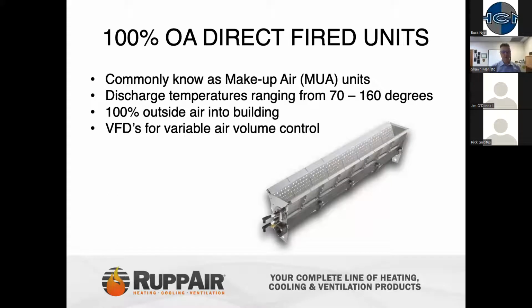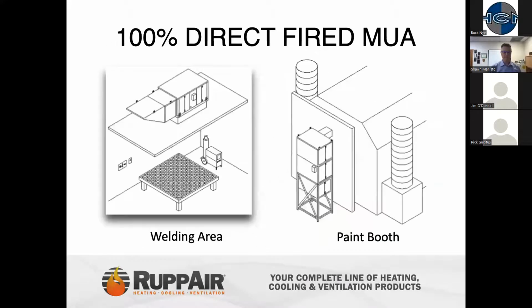Commonly they can have VFDs to allow some level of variable air volume control. So if you have a unit designed for 10,000 CFM with a VFD, you could have some variable control and vary that down to as low as 5,000 CFM. Commonly, 100% direct fired makeup air units are seen where areas of exhaust exist. In the case of this warehouse we're talking about today, maybe they put a welding bay in this area, or they have a paint booth system. These are common areas where anytime we exhaust air out, we need to bring air back into the building.